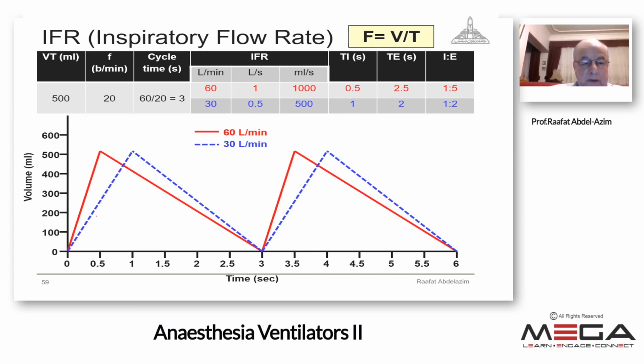If the total respiratory cycle time is 3 seconds, this means that the rate is 20. We divide 60 seconds by the rate to get the respiratory cycle time, or divide 60 by the total respiratory cycle time to get the rate. So if the respiratory cycle time is 3 seconds, the rate is 20. These 3 seconds in this example are divided into an inspiratory time of half a second and an expiratory time of 2.5 seconds. Go to the table here.